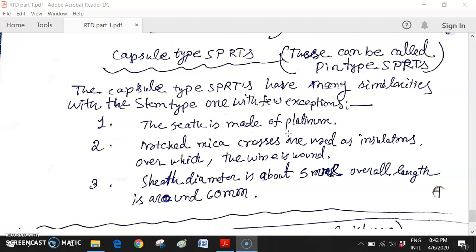That is the problem encountered with platinum - otherwise it is good, but the presence of silicon changes its chemical characteristics. Annealing is also very much necessary. So filling dry air inside the sheath and annealing - these are the common features of both capsule type and stem type SPRTs.